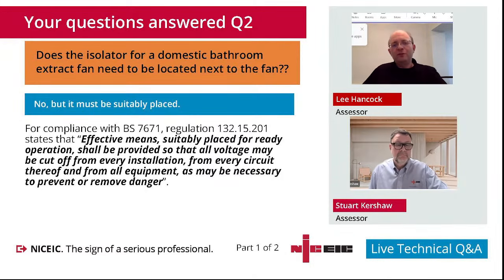So a lot of new builders nowadays specify that the isolator should be at a more localised height, usually next door to a light switch where it's readily accessible. The isolator should disconnect all live parts and live conductors, so it removes all the voltage from the fan, so it's safe to work on. Doesn't pose any dangers if a situation develops.